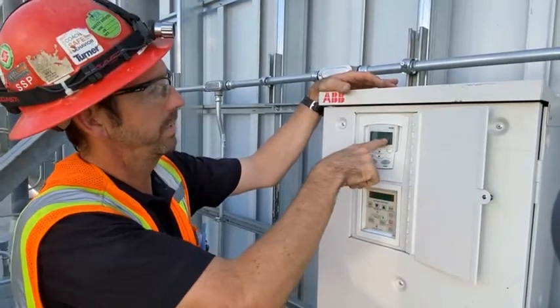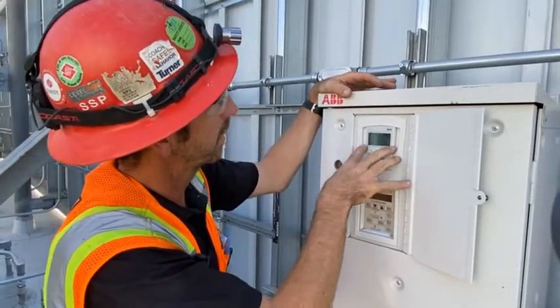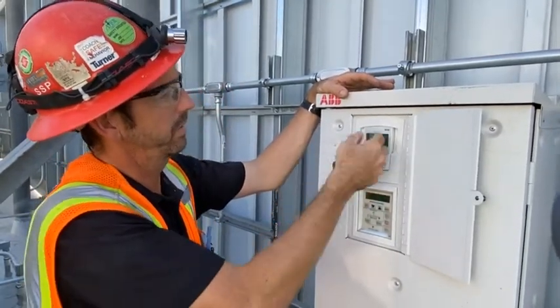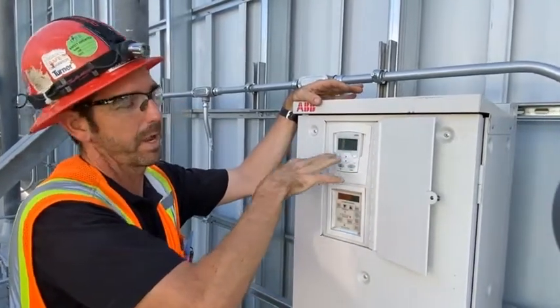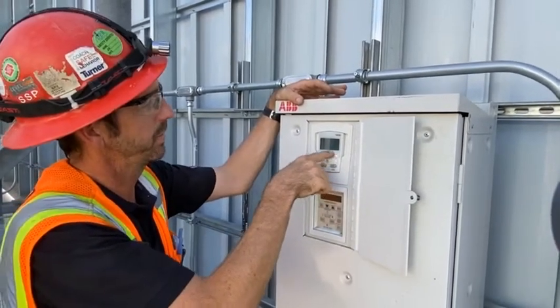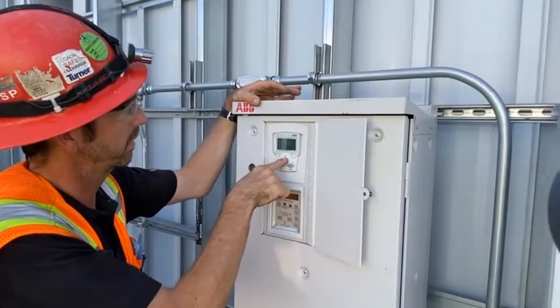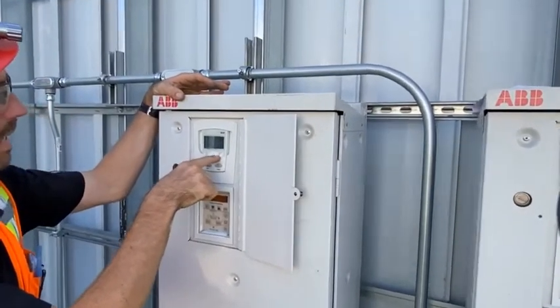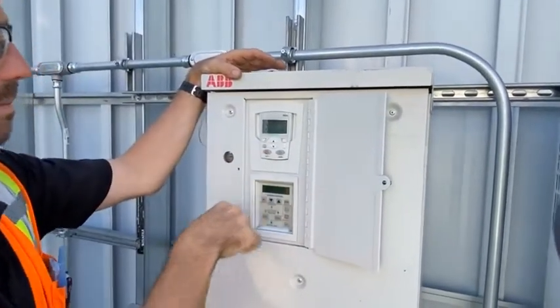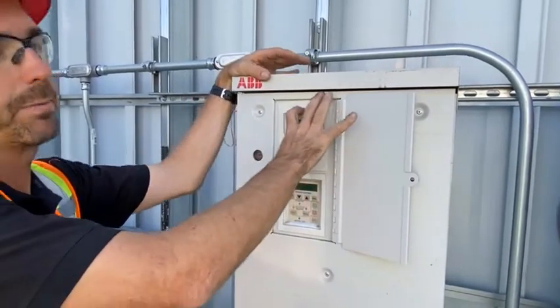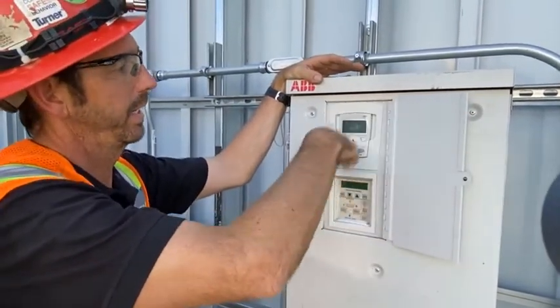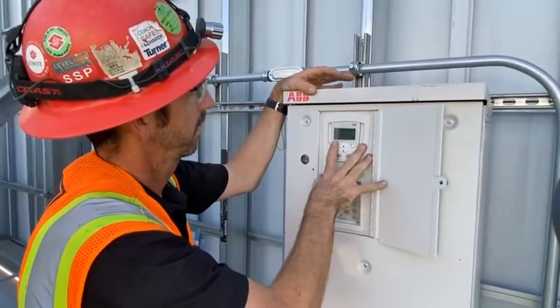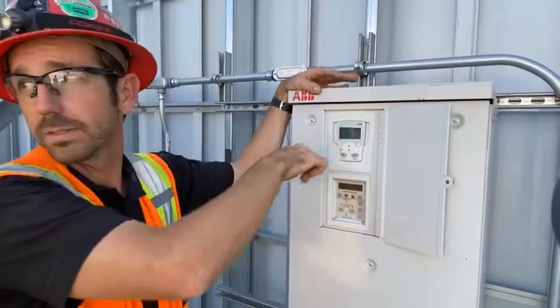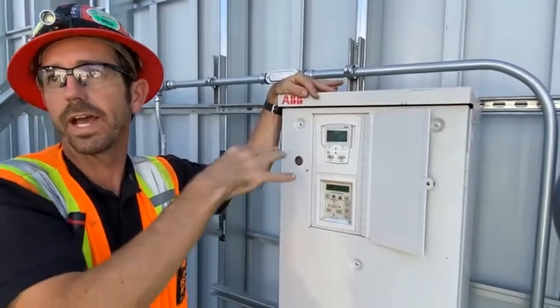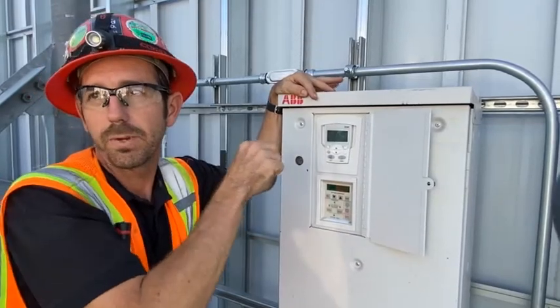So now what we want to do here, when it loaded, it took the data up into the keypad from the drive. So what we want to do is click on menu and go down to parameter backup, and we want to download the full set. We're downloading the information we saved in the keypad from over there into the drive. Now we read hertz, okay?